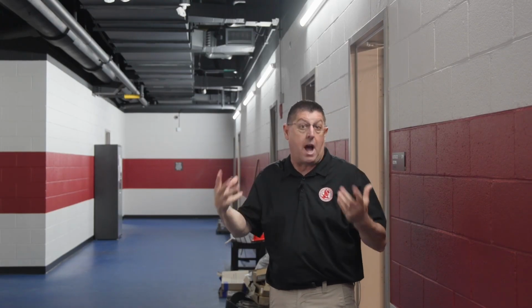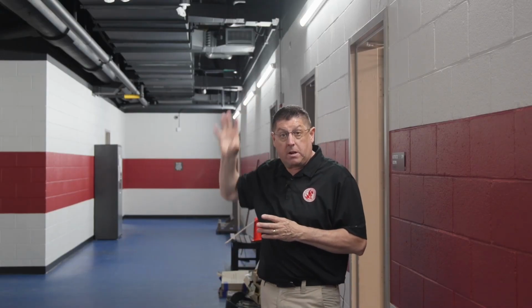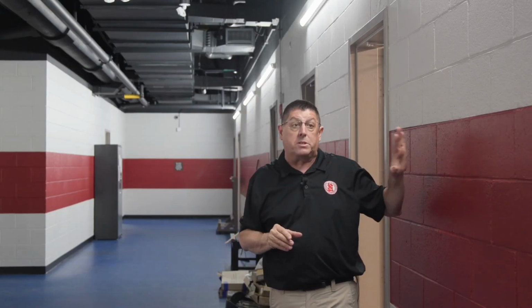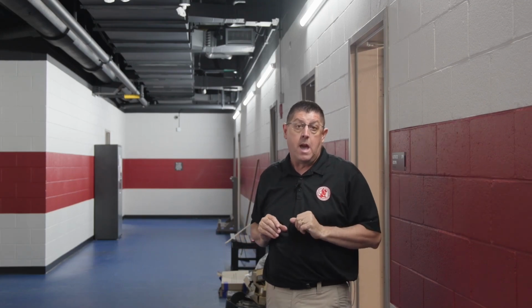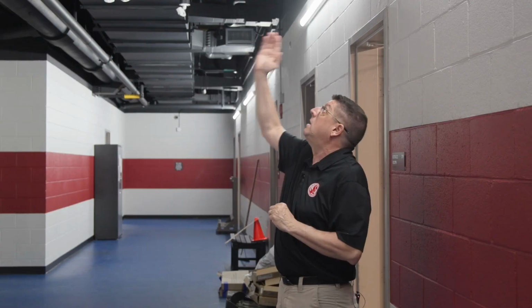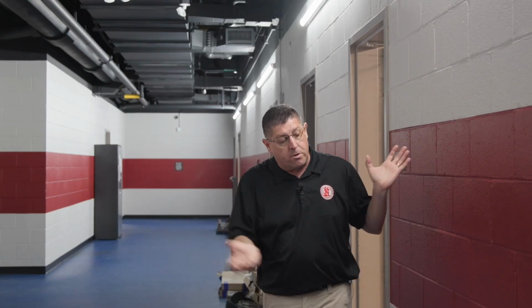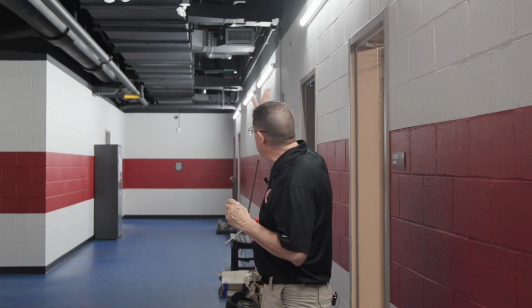Now, how they're controlled depends on the style of VAV. In our particular case, I've got a simple thermostat on the other side of this room, and it is controlling just a simple low voltage valve. And when I need heat, it opens up the valve, produces hot water, and tempers the air. Otherwise, the air is never shutting off. The air is constantly flowing and never shuts off in this entire building, and that goes down the line.